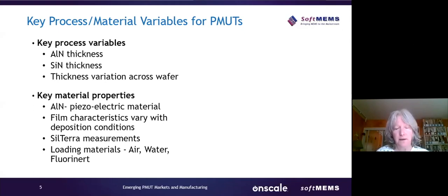And one of the things that Ian will also point out is that once we have the PMUT and its material properties understood, we have to look at what's loading the PMUT when we are simulating it in situ in an application. So for example, you'll see later some results in air, and we'll talk about how those work, but then there are also the materials that the PMUT may be interacting with, water, for example, and a popular one, fluorinert.